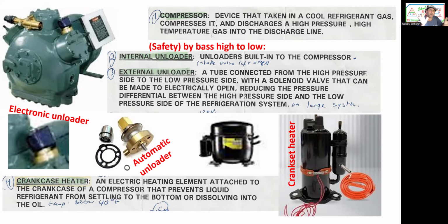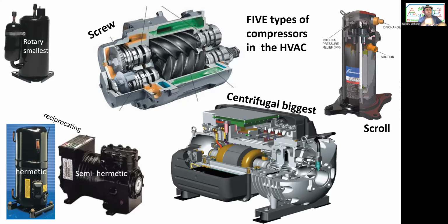Anyway, compressors. We have the rotary, which is the smallest. We have the reciprocating. I misspelled that. The reciprocating compressor has pistons going up and down, and we have the hermetic and semi-hermetic. Hermetic is a Latin word for secret or hidden, because the inside is hidden. So rotary is smallest, reciprocating is next. Then scroll, and there are many ways of scroll modulation. The two biggest ones are screw, and the biggest one is centrifugal. The screw and centrifugal, I never worked on.